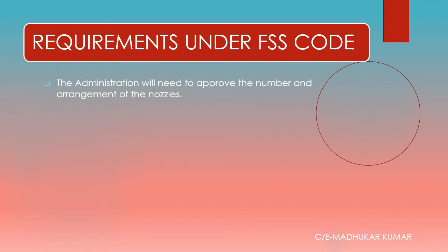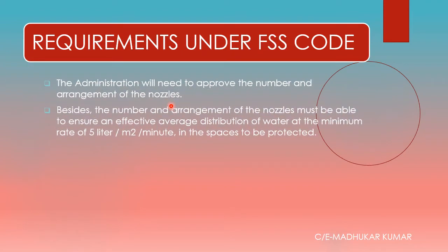As per SOLAS guidelines, the administration needs to approve the number and arrangement of nozzles. Once approved by the administration, the system must be able to ensure the effective average distribution of water at the minimum rate. This rate is important and often asked in MCQs — it is five liters per meter square per minute in the space to be protected.